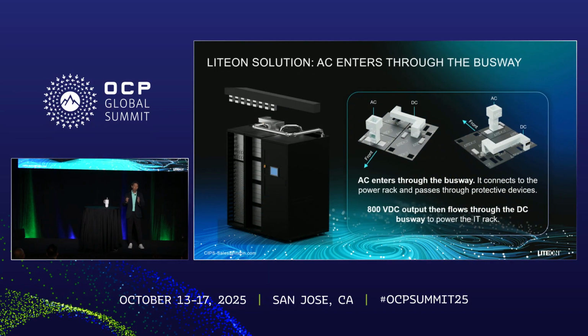There's a lot of things we are doing to enable this solution. Just to quote a few examples: first, the safety of distributing a high voltage DC bus in a system. We have incorporated the safety protection device into our busway so that we ensure we are meeting all the compliance requirements for safety in distributing the 800 volt DC.